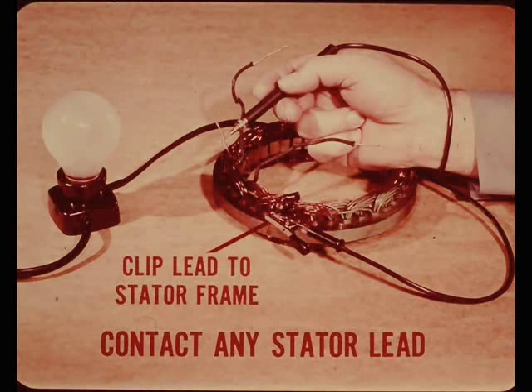Good points, Tech. Now, with the stator leads disconnected, remove the stator from the end housing and check it for grounds. With the stator on an insulated surface, clip one lead of the 110 test lamp to the stator frame and connect the other to any stator lead end. If you get a light, one or all of the windings are grounded.